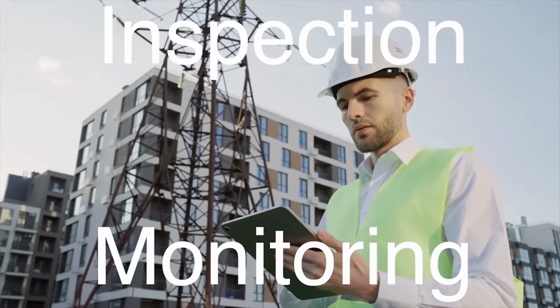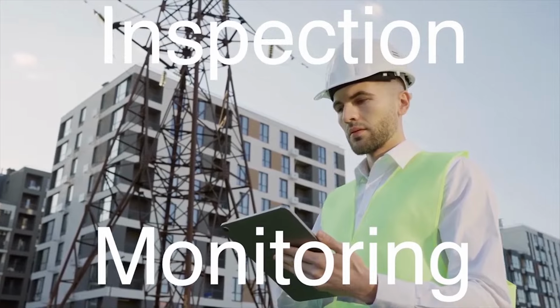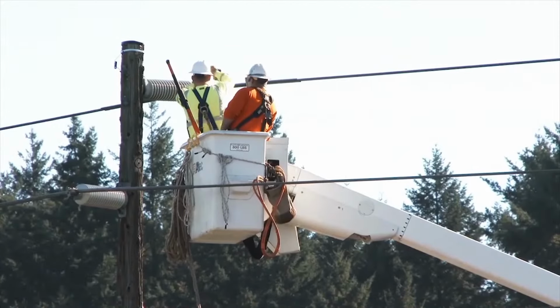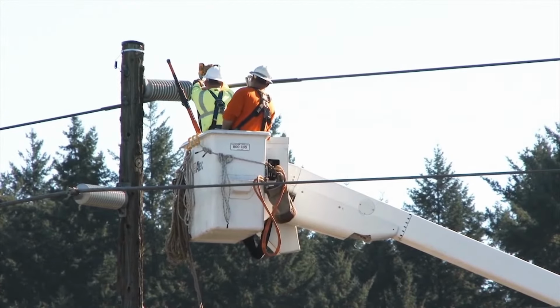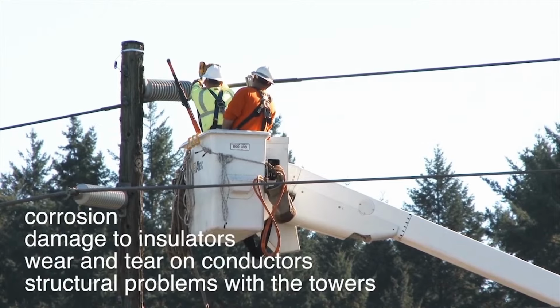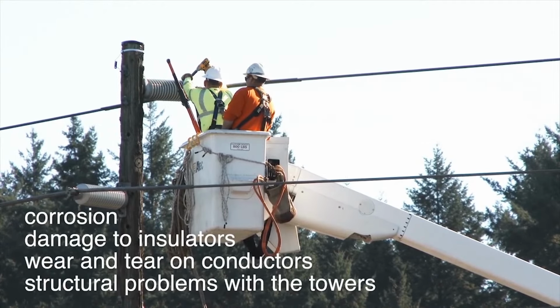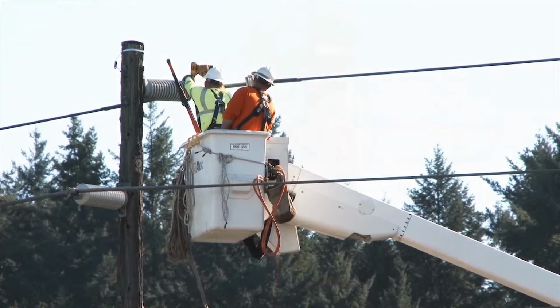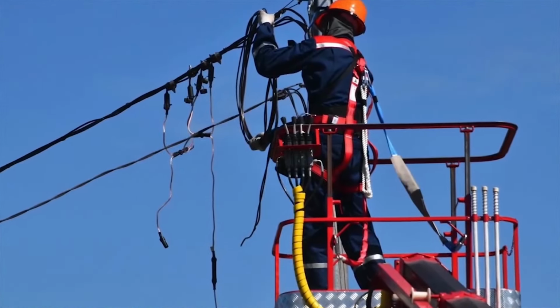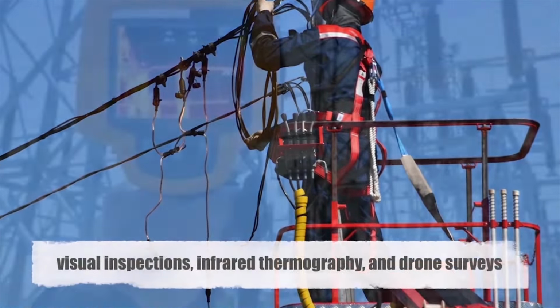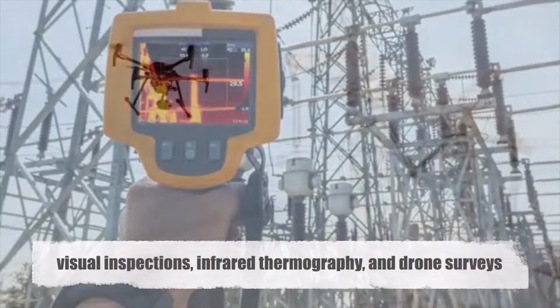Inspection and monitoring are the first steps in maintaining high-voltage power lines. Regular inspections help identify potential issues like corrosion, damage to insulators, wear and tear on conductors, and structural problems with the towers. These inspections can be performed in several ways, including visual inspections, infrared thermography, and drone surveys.